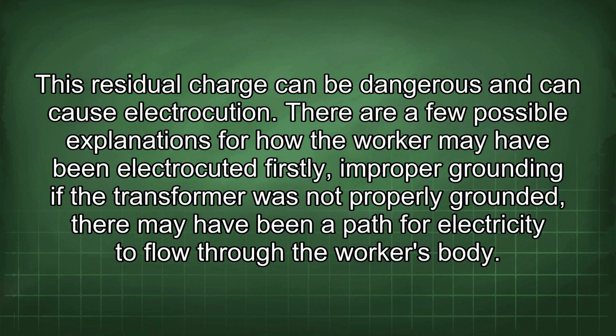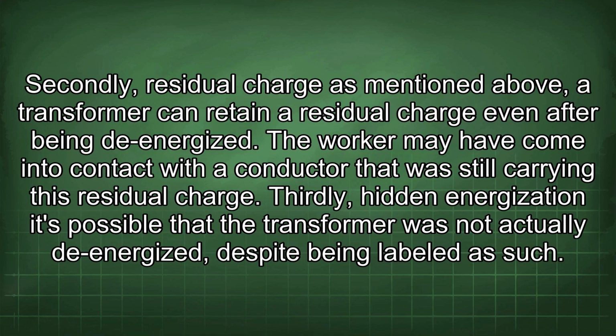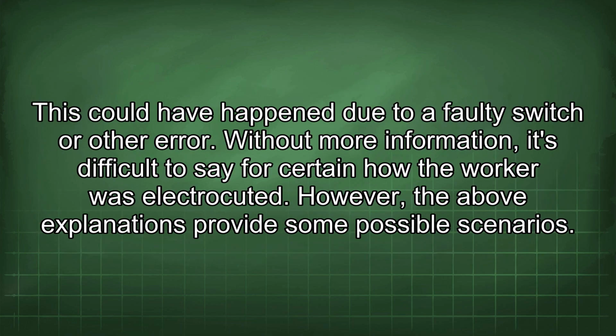There are a few possible explanations for how the worker may have been electrocuted. Firstly, improper grounding. If the transformer was not properly grounded, there may have been a path for electricity to flow through the worker's body. Secondly, residual charge, as mentioned above. A transformer can retain a residual charge even after being de-energized. The worker may have come into contact with a conductor that was still carrying this residual charge. Thirdly, hidden energization. It's possible that the transformer was not actually de-energized, despite being labeled as such. This could have happened due to a faulty switch or other error.